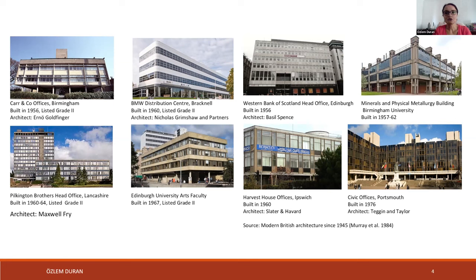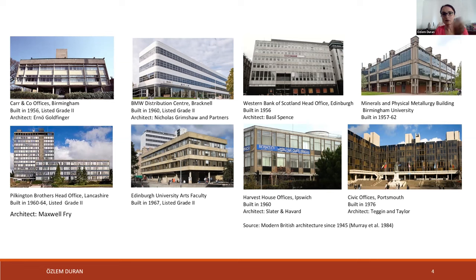In addition to high energy consumption, occupants of these buildings suffer from thermal discomfort because of the poor envelope. No matter how high the air temperature is, the operative temperature — the average of radiant and air temperature — cannot reach the thermal comfort levels required by regulations, especially for those who sit around the perimeter of the building. Because of the low radiant temperature, they continuously feel cold or warm. And although it's a subjective judgment, these buildings also have aesthetic problems.